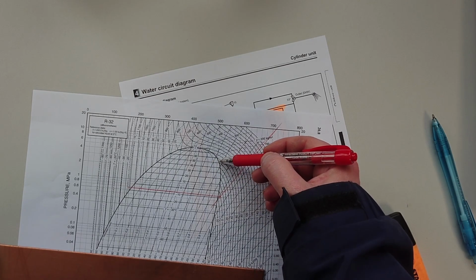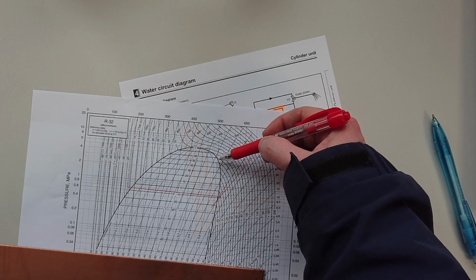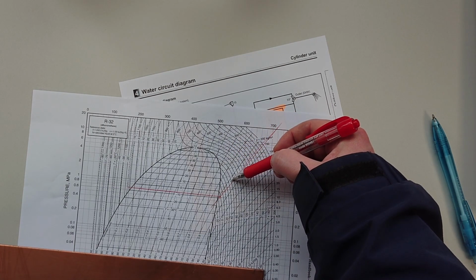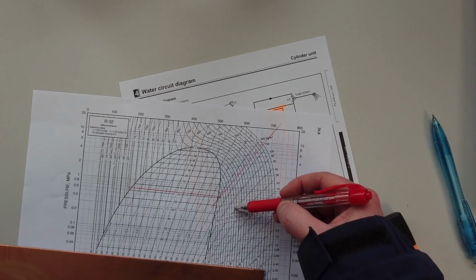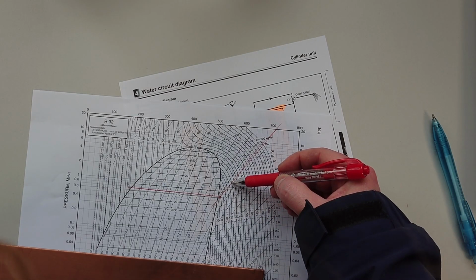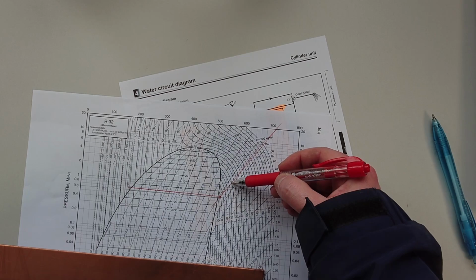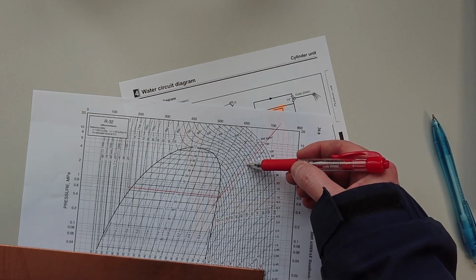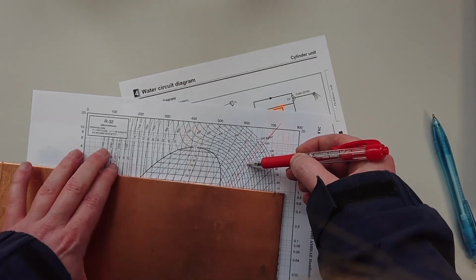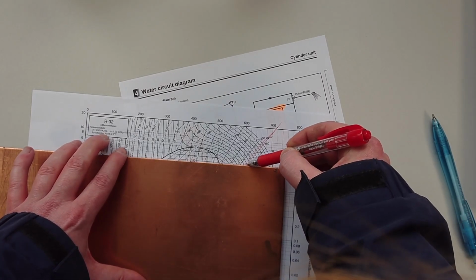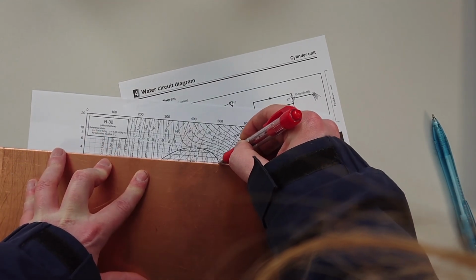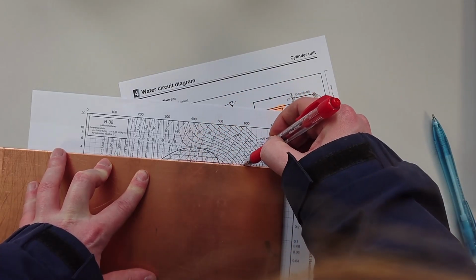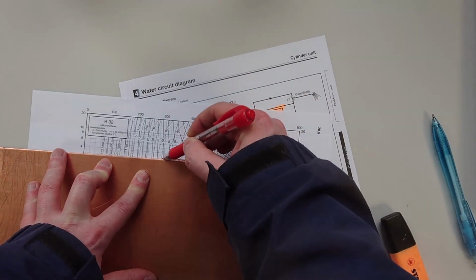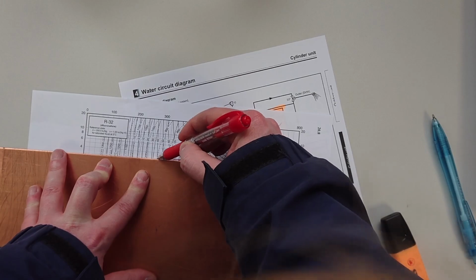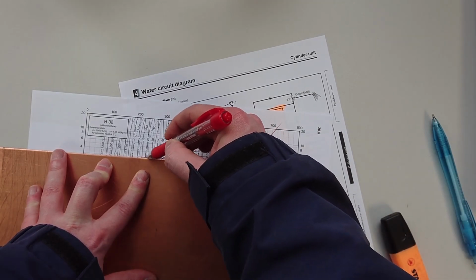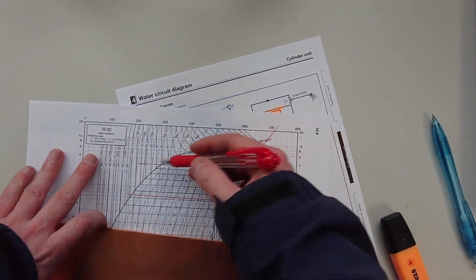And 50 goes to... where's 50? 50 goes there. So we're condensing there, and we're over here on the line. So what we need to do then is reject this heat, and then now we go through the heat exchange in the heat exchanger, and we condense and lose all the energy that's now going into your water to heat your house. And then it drops down to like it's not going to get to 0, but we've got to go past it, and we end up with subcooling.